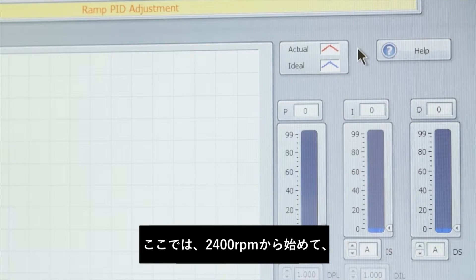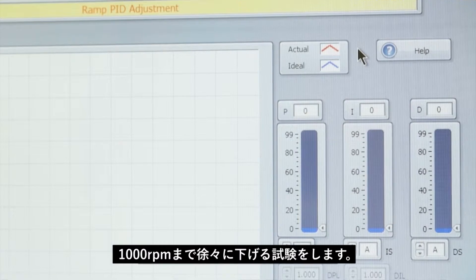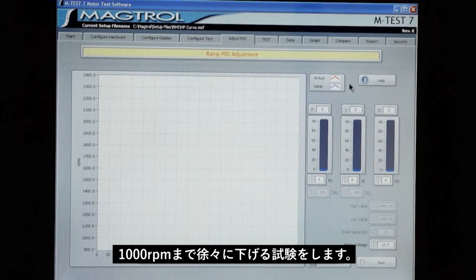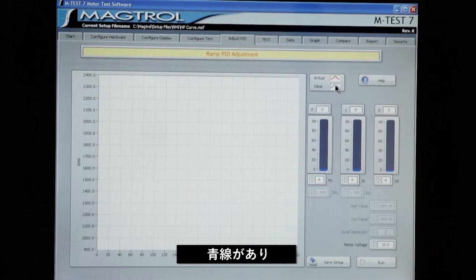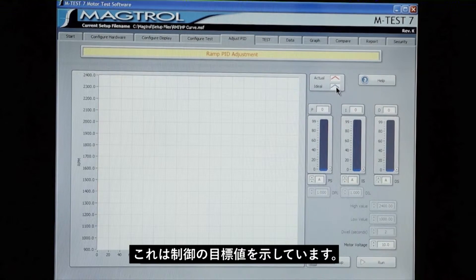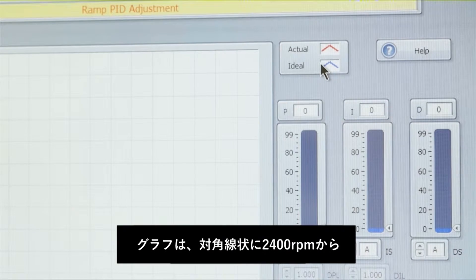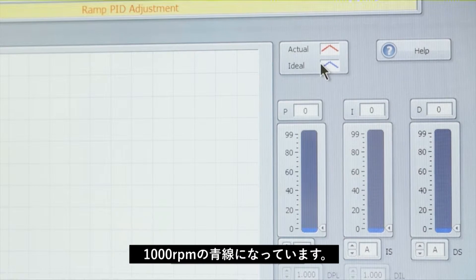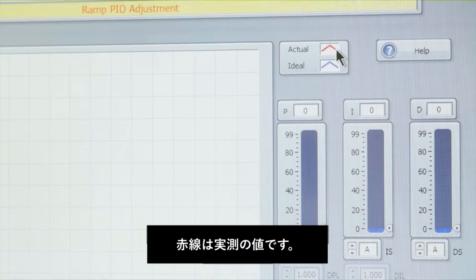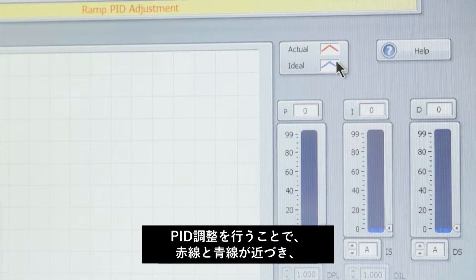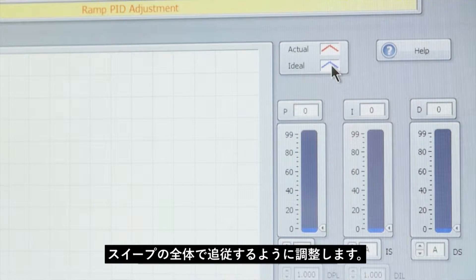In this case we're going to start at 2400 RPM and ramp down to 1000 RPM. What the graph will show with the blue line is the ideal system response — a diagonal line from 2400 RPM down to 1000 RPM. The red line is your system response, and your goal is to make the red line follow the blue line for the majority of the sweep.